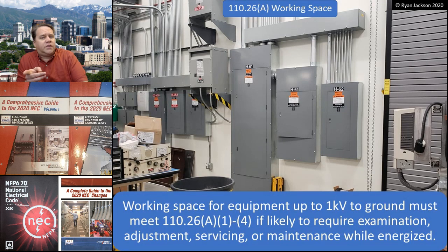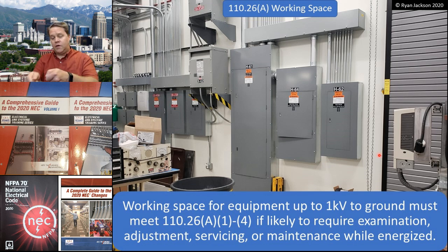So we look at 110.26(A). It says working space for equipment up to 1,000 volts to ground must comply with A1 through A4 if it's likely to require examination, adjustment, servicing, or maintenance while energized. Now, looking at this photograph, I think most people agree that a panel board meets that criteria. At some point, somebody is going to have to examine, adjust, service, or maintain that piece of equipment while it's energized, even if that is just a matter of verifying the presence or absence of voltage.